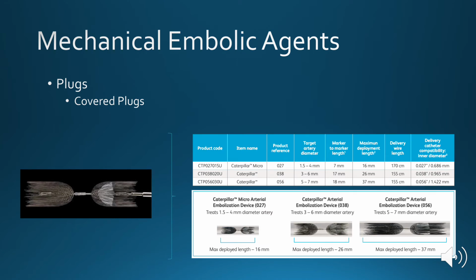There are 3 different models of this plug covering different size vessels, with the first model, the 027 device, being appropriately used in 1.5 to 4 millimeter arteries. The second device, the 038 device, goes into vessels 3 to 6 millimeters in diameter. And the third device, which is the 056 device, goes into vessels 5 to 7 millimeters in diameter. You should recognize that the name of the device corresponds to the inner diameter of the catheter that you need to deliver the device where it needs to go.